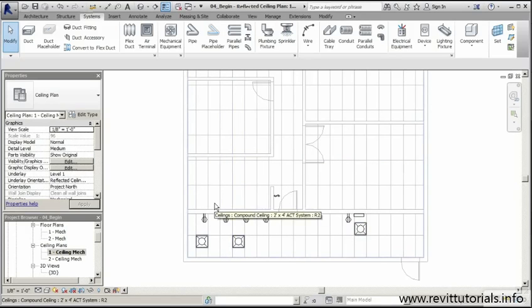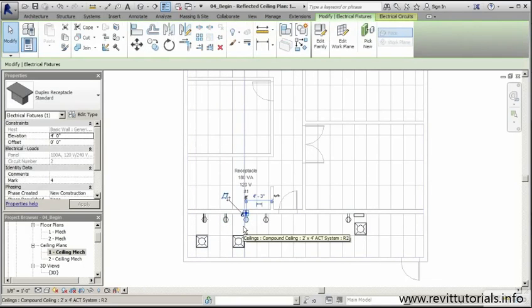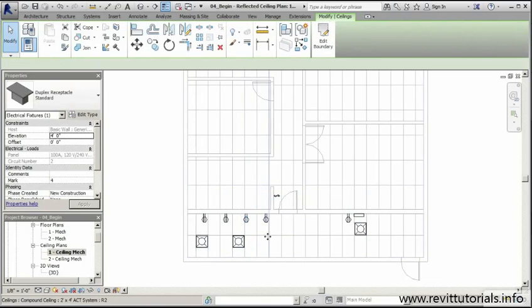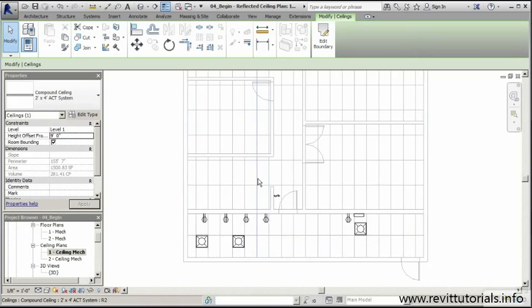but I'm also going to need something maybe to plug into my range. So let's get started by doing a quick calculation that's going to let me know that the loading on this circuit is going to be okay. When I click on any one of these here, you see two numbers, and these two numbers are going to be very important to us when we're doing our calculation. The first is this 180, and the second is this 120 volts. So what we need to do is we know that we have a 20 amp system here, or circuit, and we want to know exactly how many outlets we can have without overloading this system.